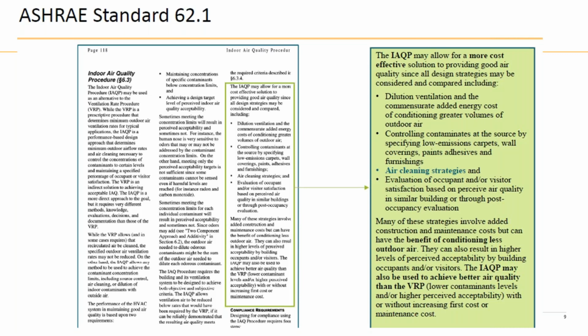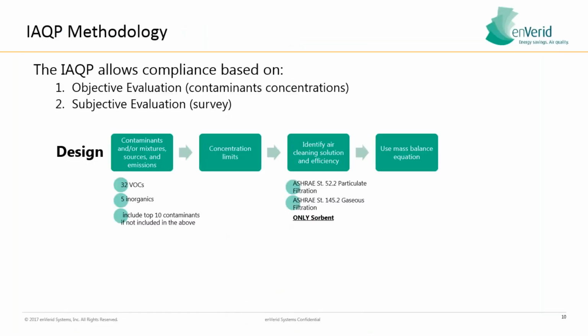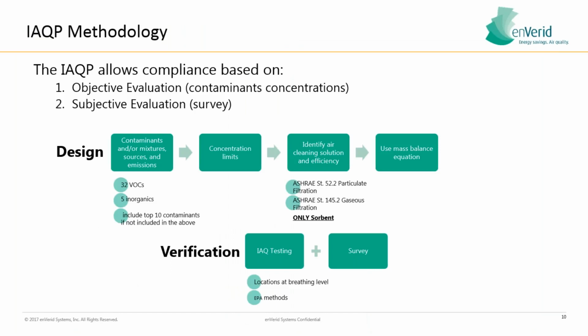You receive the benefit of conditioning less outdoor air, and it may also lead to higher levels of perceived acceptability and indoor air quality. So you can use this methodology, this calculation, which exists within ASHRAE 62.1, to achieve better indoor air quality than the ventilation rate procedure. Big changes. So let's talk a little bit about what the indoor air quality procedure is. Basically, it addresses a full list of contaminants. Right now, that contaminant mix is 32 VOCs, 5 inorganics, and top 10 contaminants if not included in the list above. An engineer will set the concentration limits.